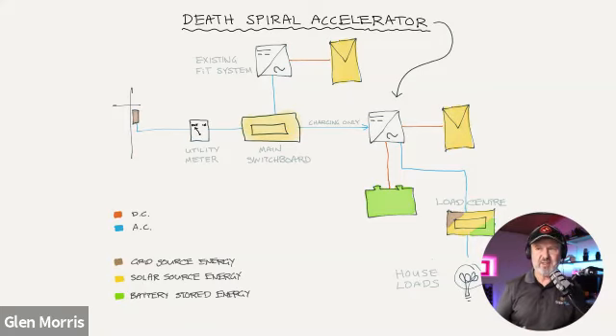I should point out there are products available that do this very cheaply. Thinking of a brand name, MPP Solar makes one. In Australia, they sell for about $900 Australian. It's a 5 kilowatt inverter that can take about 7 kilowatts of solar, with a 48 volt battery, and it's very cheap. But it needs no certification to connect as an appliance to the grid because it's only a load, only a battery charger.